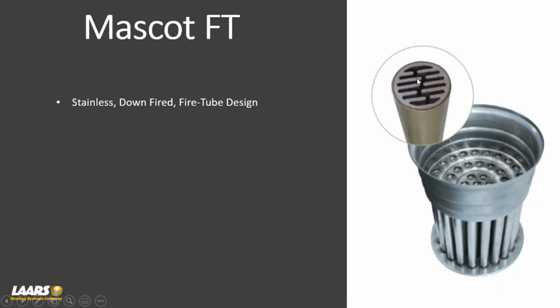Now, these tubes are sleeved with an aluminum coating. Why aluminum? Because aluminum transfers heat 5 times faster than stainless. So as the heated flue gases are traveling down these tubes, we're absorbing that BTU and transferring it right to the stainless that is in your flue passage.